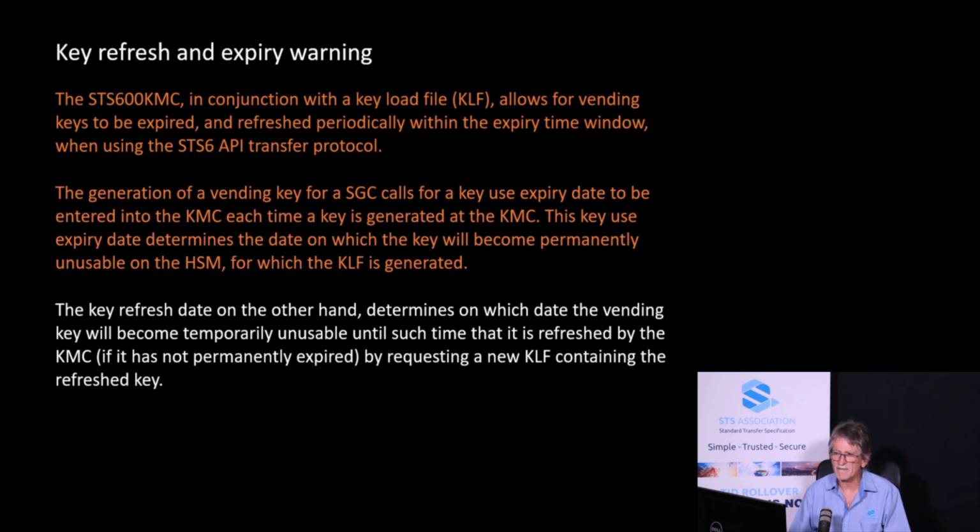The generation of a vending key for a supply group code calls for a key use expiry date to be entered into the KMC each time a key is generated by the Key Management Center. This key use expiry date determines the date on which the key will become permanently unusable on the security module for which the keyload file is generated.